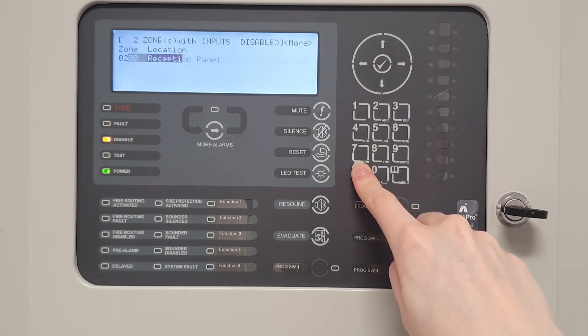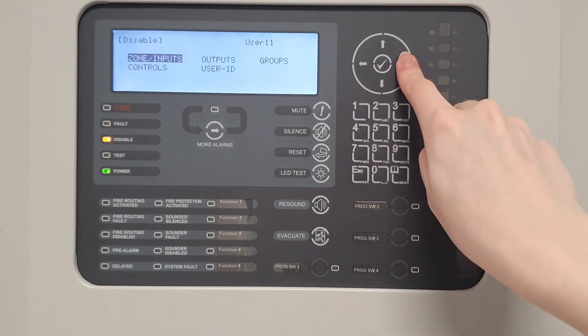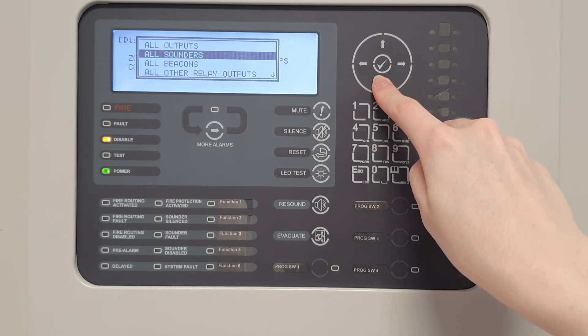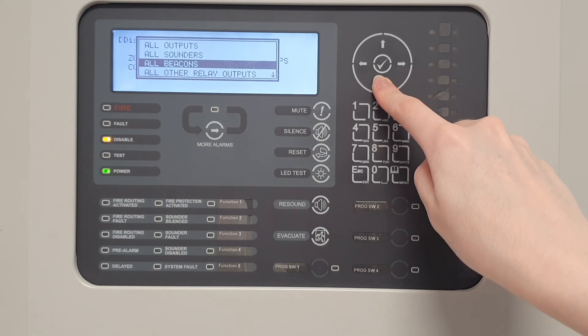To disable outputs, select outputs from within the disable menu, then select which outputs from the list. Selecting all outputs will disable all sounders, beacons and relays. Selecting all sounders will only disable sounder style outputs. Selecting all beacons will disable all beacons. And selecting all other relay outputs will disable all relays on the system.